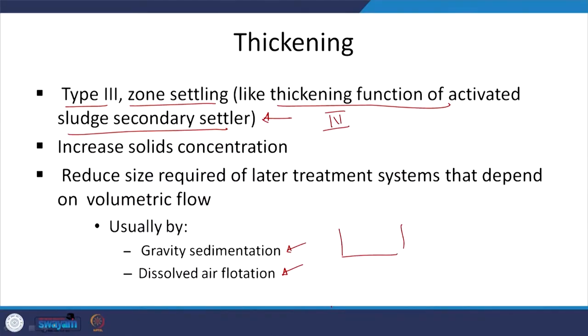If the flocs are relatively more buoyant, then rather than trying to settle them down you will invert the process: you introduce air under pressure so that these buoyant sludge particles move up to the surface where they are removed. In gravity sedimentation, the interface moves down — relatively clear water on top, high solids concentration below. In dissolved air flotation, air is introduced under pressure, bubbles form, they go up and carry buoyant solids with them, and you can remove the solids at the top — it is an inverse of gravity sedimentation.